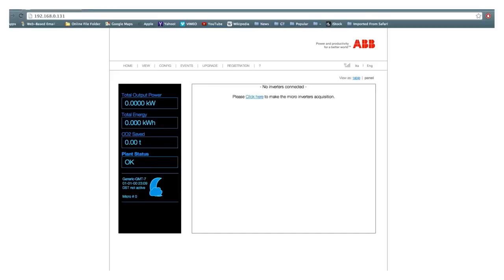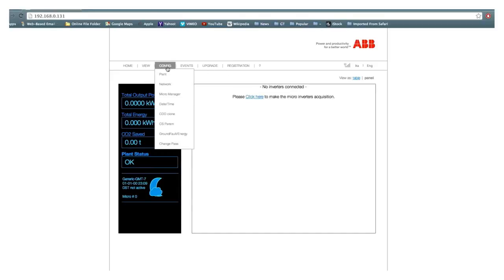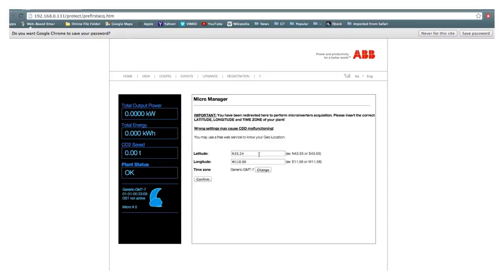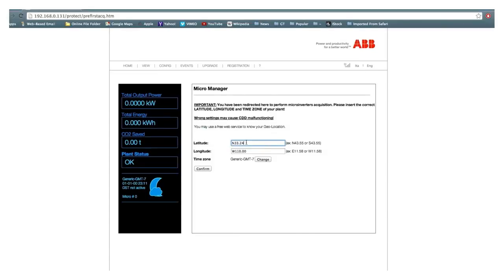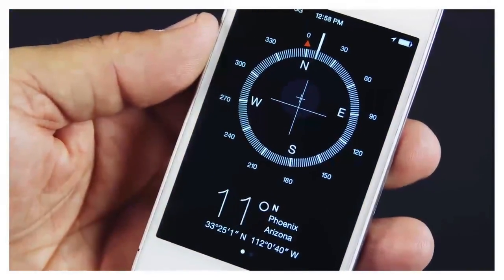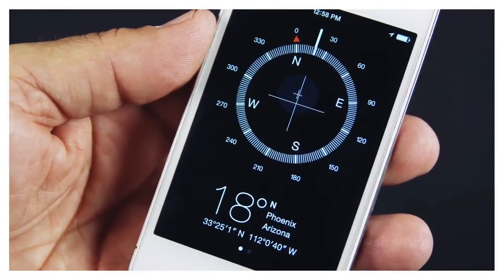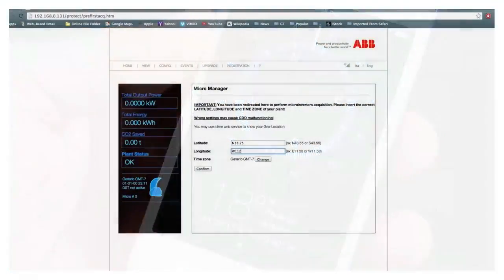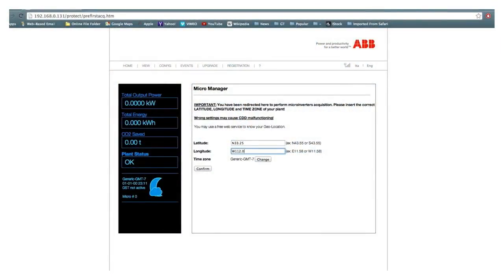Navigate to the Micromanager page from the Config menu. A pop-up menu will appear asking for further authentication. Enter 'admin' for the username and 'admin' for the password, all lowercase letters. The micromanager will ask for the latitude, longitude, and time zone of the installation location. You can find this by Googling the address or looking at a Compass app on your smartphone. This step is very important — if not done correctly, there may be problems with system monitoring. Enter the correct information and click Confirm.